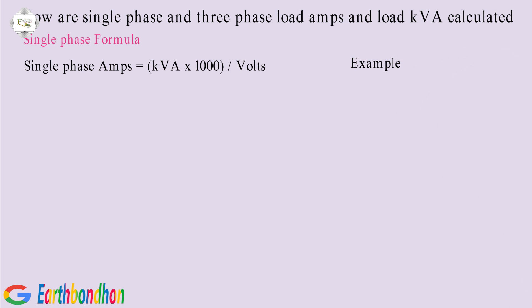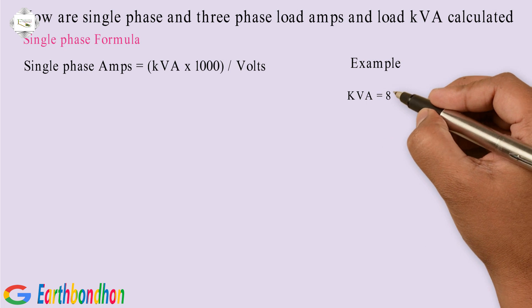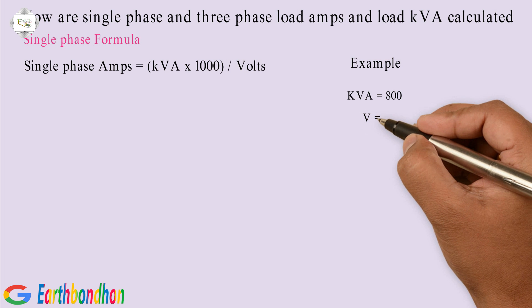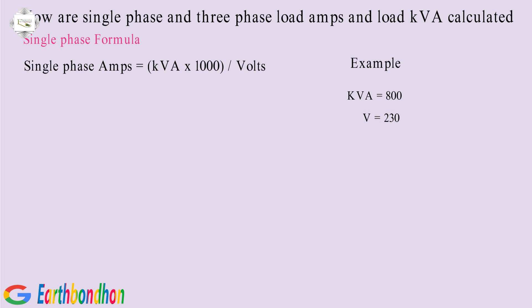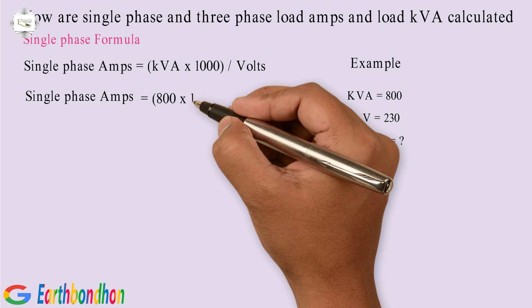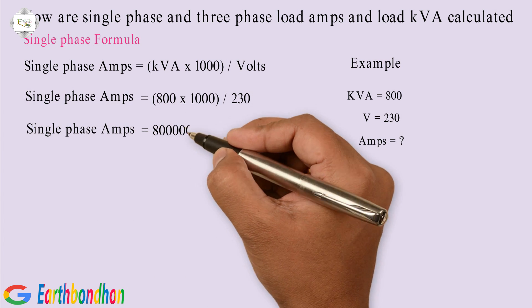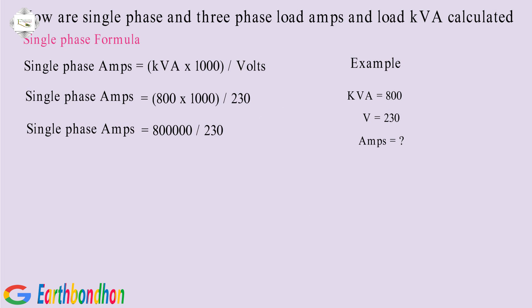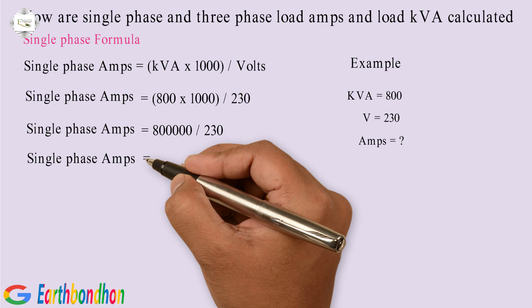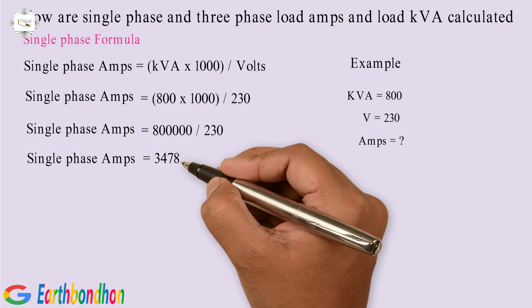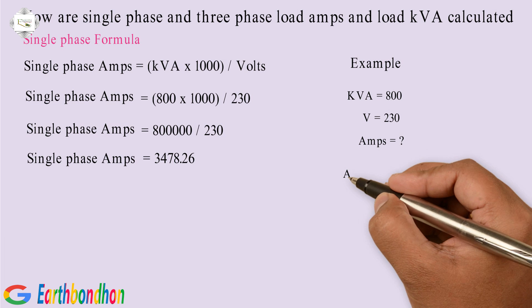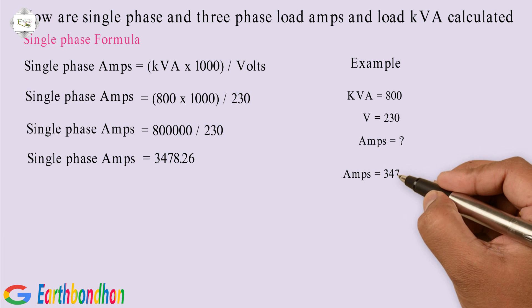Example: KVA equals 800, V equals 230, amps equals unknown. Amps equals 800 multiplied by 1000, divided by 230. Equals 800,000 divided by 230. Equals 3478.26 amps.